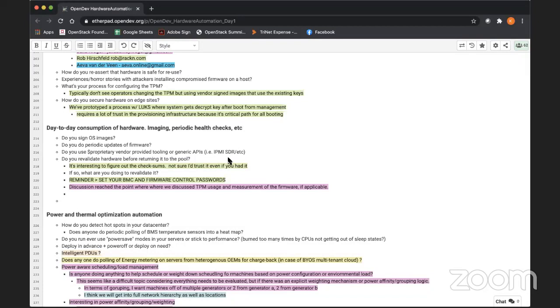And the temperature discussion was, I've had temperature drops and we've sent people over to the data center. What the hell is going on? It was a small system, and every month it would happen, and we finally figured out, that's the AC guy. He's shutting off the blowers and replacing those filters, and the blowers are down for like 2 minutes, and then he's gone, and then we go in.